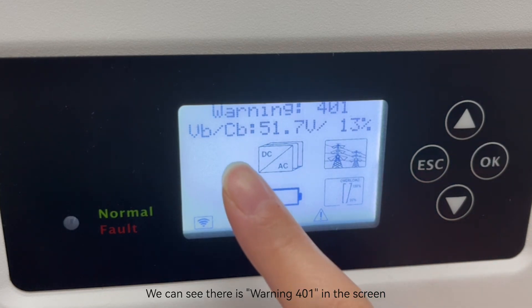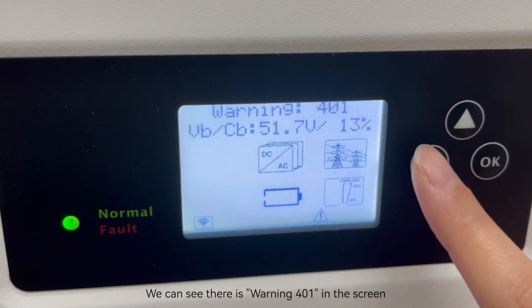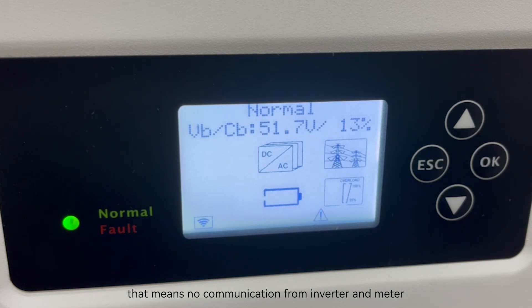If warning 401 appears on the screen, that means there's no communication between the inverter and meter. Double check the wiring of the meter.